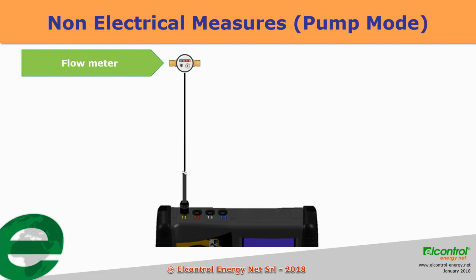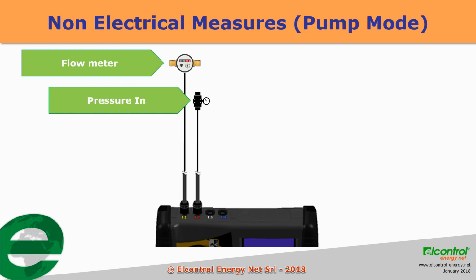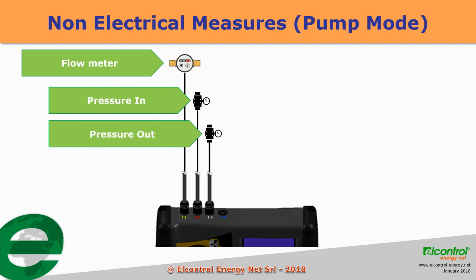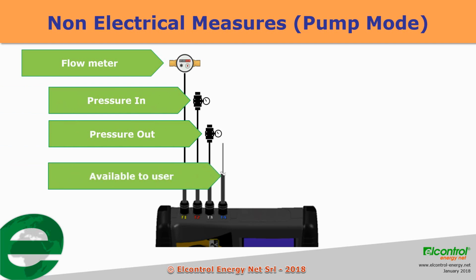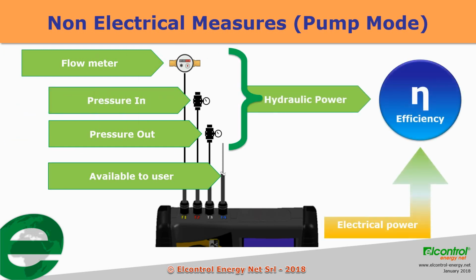Pump mode is aimed to measure pumping system parameters as well as overall efficiency. When pump mode is selected, NanoVIP 2 Plus will expect a flow meter connected to input T1, an inlet pressure sensor on input T2, and an outlet pressure sensor connected to input T3. T4 input remains available for any additional measure the user needs. With measures from inputs T1, T2 and T3, NanoVIP 2 Plus calculates hydraulic power. Electrical pump power is measured by the electrical channel. NanoVIP 2 Plus is then capable of calculating real-time pumping system efficiency.